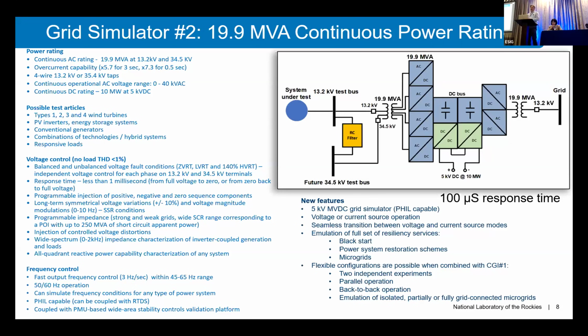And we also added, as part of the build, an up to 5,000 volt, 2,000 amp bidirectional DC power supply. So a good application. We're hoping to use it for some of these newer, possibly 800 volt data center power systems. Yeah, voltage quality is really good on these. We have output filters that keep our voltage THD below 1%, no load.